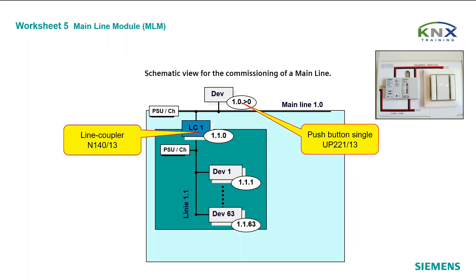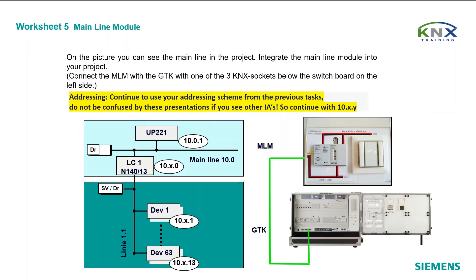The given scheme is only an example based on the assumption that someone has used line 1.1 so far. If you are using a different line, make sure to adopt the given figures. You can see the main line in the project picture. Integrate the main line module into your project and connect it with the Gamma training kit with one of the three KNX sockets below the switchboard on the left side. Continue to use your addressing scheme from the previous tasks — do not be confused by other individual addresses shown; continue with 10.x.y.